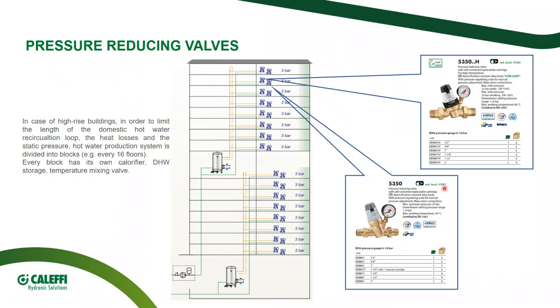And this is valid for both hot water and cold water. So this is a cross-section that you are very familiar with. This is a high-rise building where, of course, the hot water and cold water distribution systems are divided by parallel sections. I think the average is once every 16 floors. So every 16 floors, I have a calorifier, I have a smaller hot and cold water distribution system that I have to manage with pressure reducing valves.